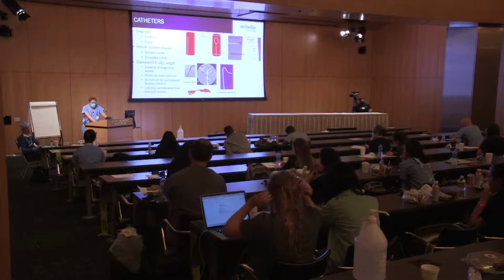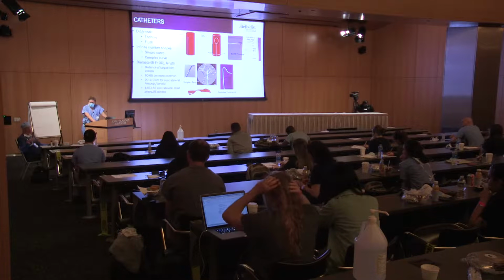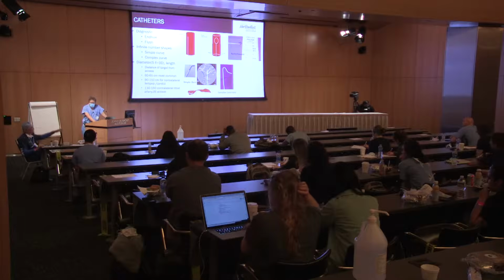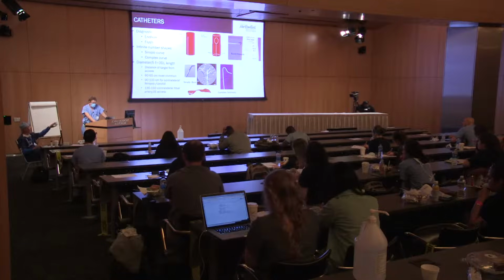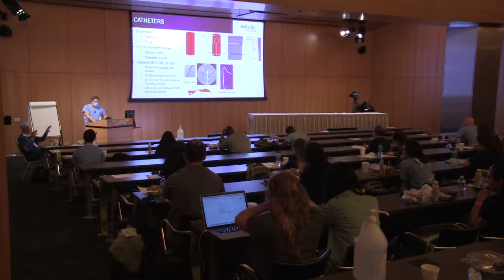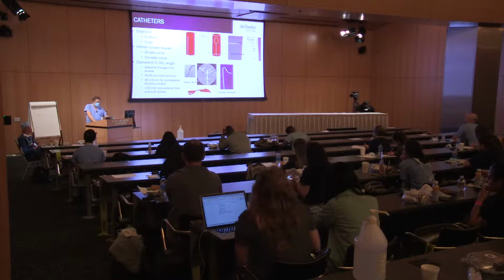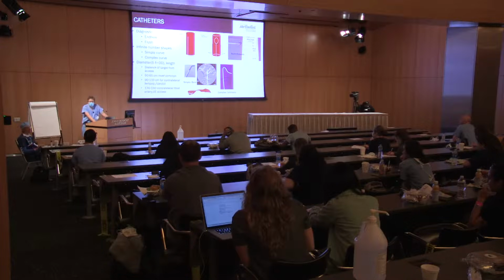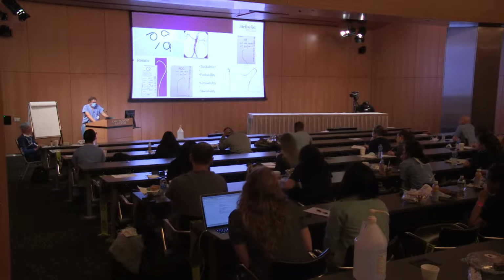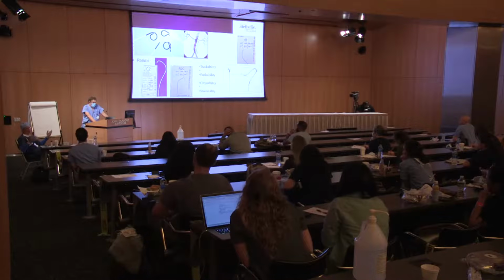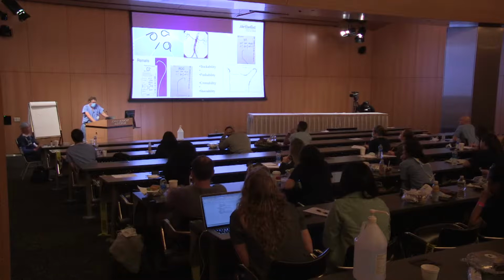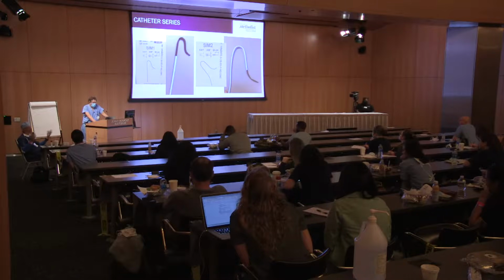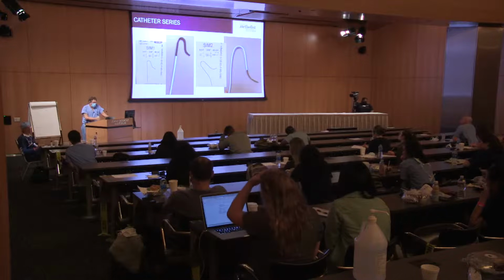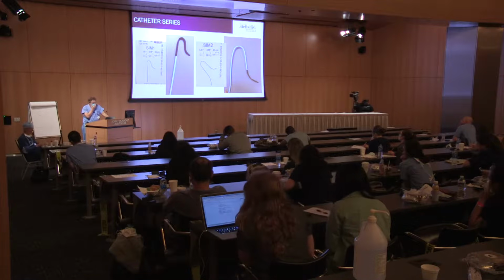It's a safety limit. So you can put it at 800, 900, 1100. You'll almost never go over it. But the easiest thing to do is look on the label. Every one of those catheters has a defined burst pressure, and that's actually the pressure you should use if you want to be technically safe. That's the safe thing. 20 for 40 at 800 is going to get you through 90% of these things if you want to do it that way. 15 for 20, whatever you're injecting, at 800 is going to be safe. But it's not the pressure you're injecting, it's a pressure limit that's set on the machine.